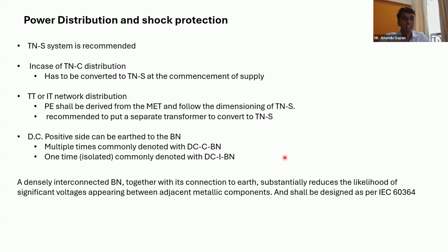And then this is for the AC side. When you come to the DC side, generally you have two kinds of system. I'm not talking about the DC side TNS, TNCS or anything like that. You can go with the TNS itself. But when you come to the DC side, you have your positive and negative, right? So when you have your positive and negative or your midpoint, there are two things which come into play. Either you can earth it a single time, which is called isolated earthing, or you can earth it multiple times, which is called multiple earthing.